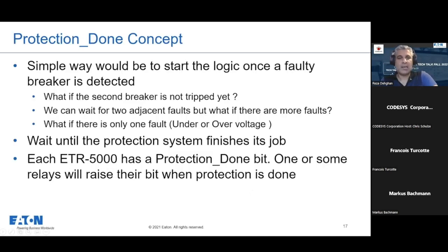Okay. Yeah, the concept of protection done. One simple way to do this is to start the logic once a faulty breaker is detected. But there are some problems with the system. What if the second breaker is not tripped yet? How do we know that the protection system has done everything that is necessary to isolate the fault?